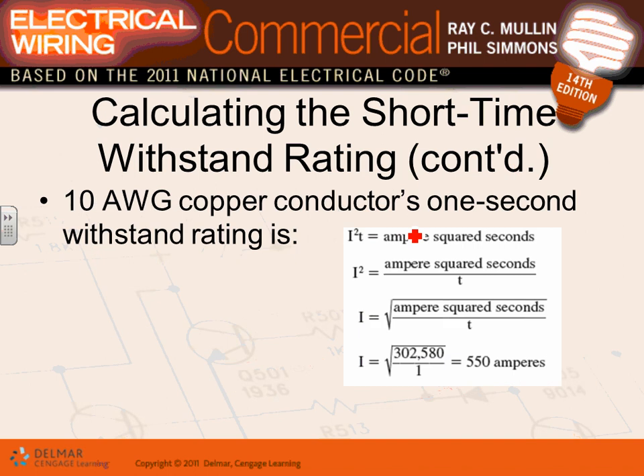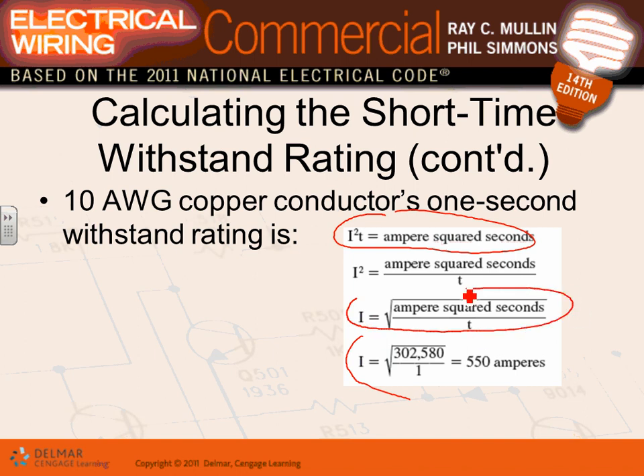You take this formula, guys, and you flip this formula, right? I hope you understand how you flip that formula. You take the square root of the amp squared seconds divided by T. Here's the number that we came up with a second ago, divided by 1 second, because Chad wants to know how much current this conductor can carry for 1 second. Gentlemen, a number 10 conductor can carry 550 amps for 1 second. You put 2 seconds on that baby, what's going to happen? Completely burn it. So these are what they call the withstand rating for conductors.